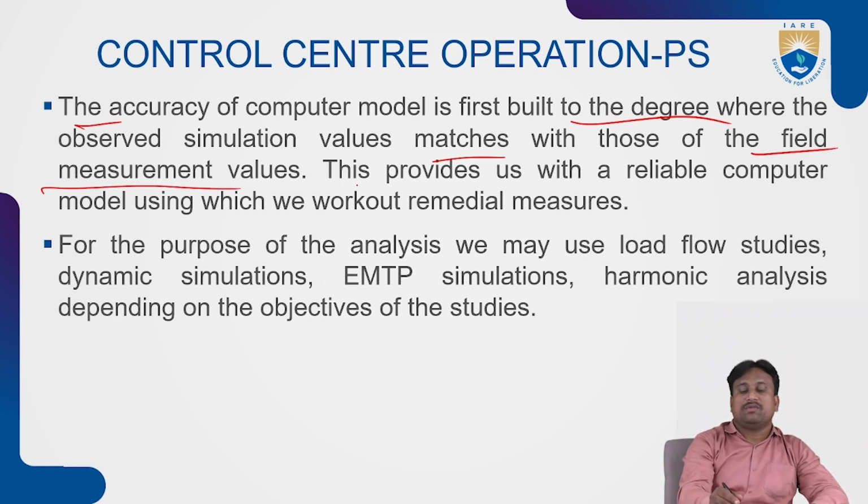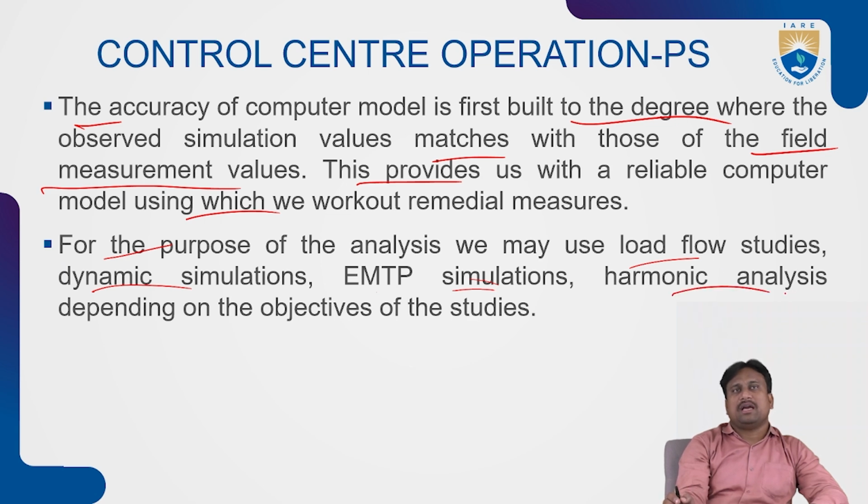That will provide us with a reliable computer model to work out the remedial measures. For the purposes of the analysis, we may use load flow studies, dynamic simulation aspects, EMTP simulations, and harmonic analysis based on harmonic considerations. Depending on the objectives of the studies, we are going to set these system parameters.